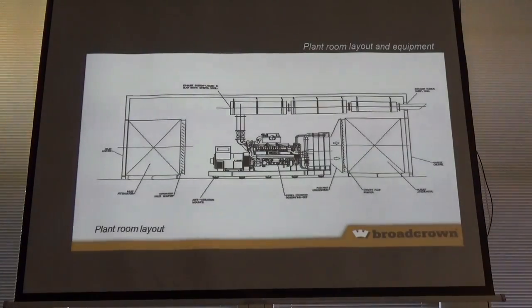They'll work out what's the average, so the daytime might be something like 75, but the nighttime might be 65. In a lot of cases, what they want to do then is say, okay, but we don't want that set, or those sets, if they're running, to contribute to the overall noise level at night. So they'll then take 10 dBA off it. So they'll say the sets need to be 55 dBA, which is horrendous with regard to the extra footprint area that's required for the inlet attenuators, the discharge, and the silencing systems.